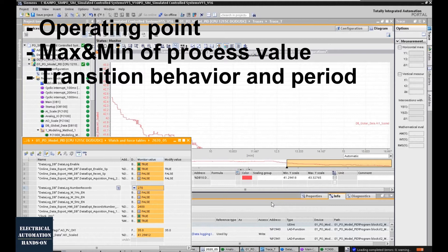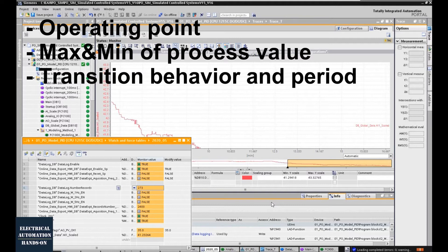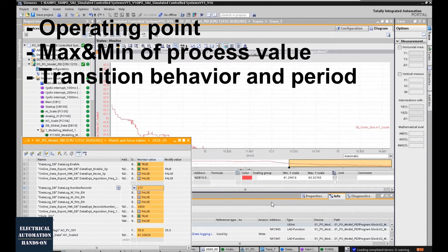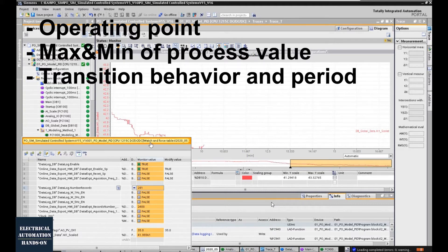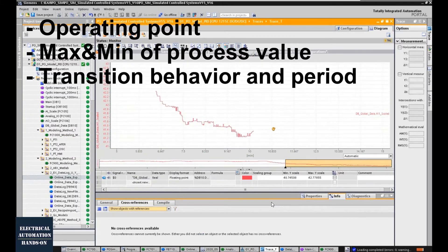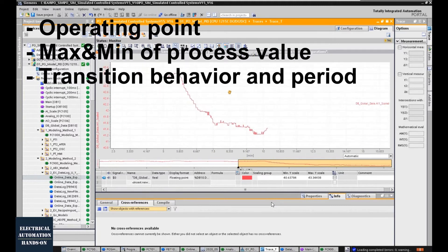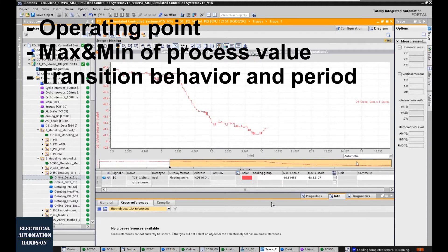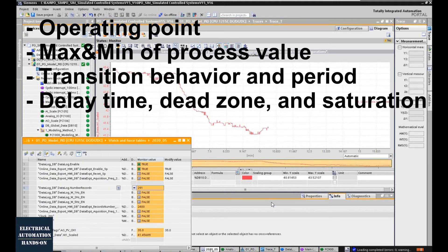And the third item is the transition time. You need to understand every time you change the actuator, how long your system will transit, and how long you need to wait. Because working on-site, sometimes the time is limited. You must understand or have a rough plan how long you could be working on-site. Maybe, totally, you could have three hours. But every time, the transition time may take one hour. That means you only have three times to change the actuator and get the response and get the rough idea of how the behavior of your system.